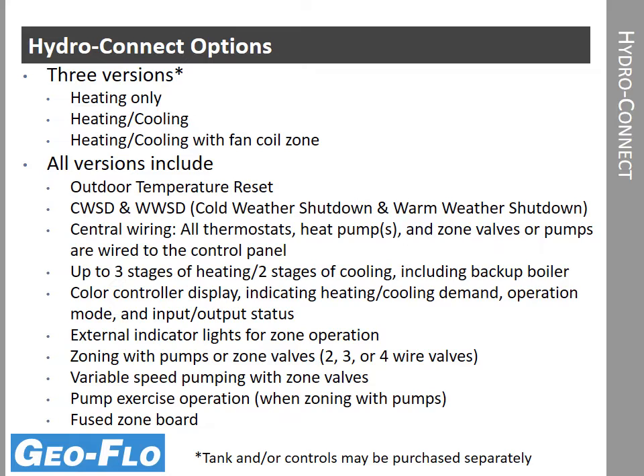The displays are full color displays, including an indication for heating and cooling demand, operation mode, and your input and output statuses, as well as external indicator lights for zone operations so that you can see which zone is calling. The zone board is set up for either pumps or zone valves, and the zone valves have several different configurations. If we're looking at variable speed pumping, that's available with one of the zone panel options and does have connections for zone valves. As the zone valves open and close, the variable speed pump then increases or decreases in speed.